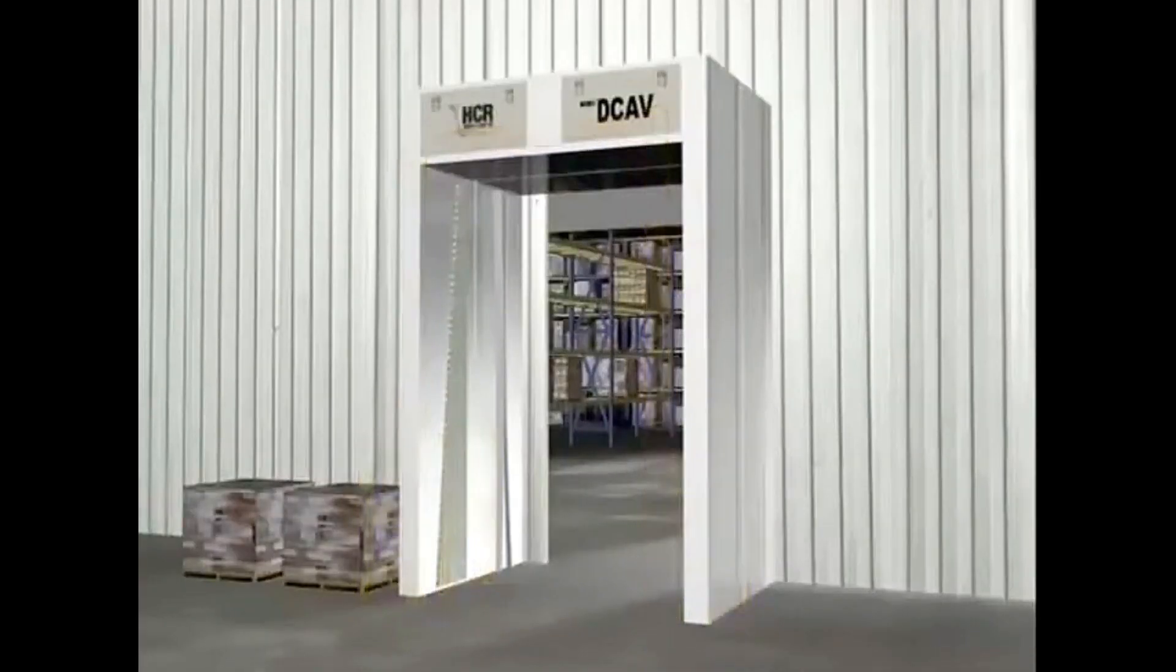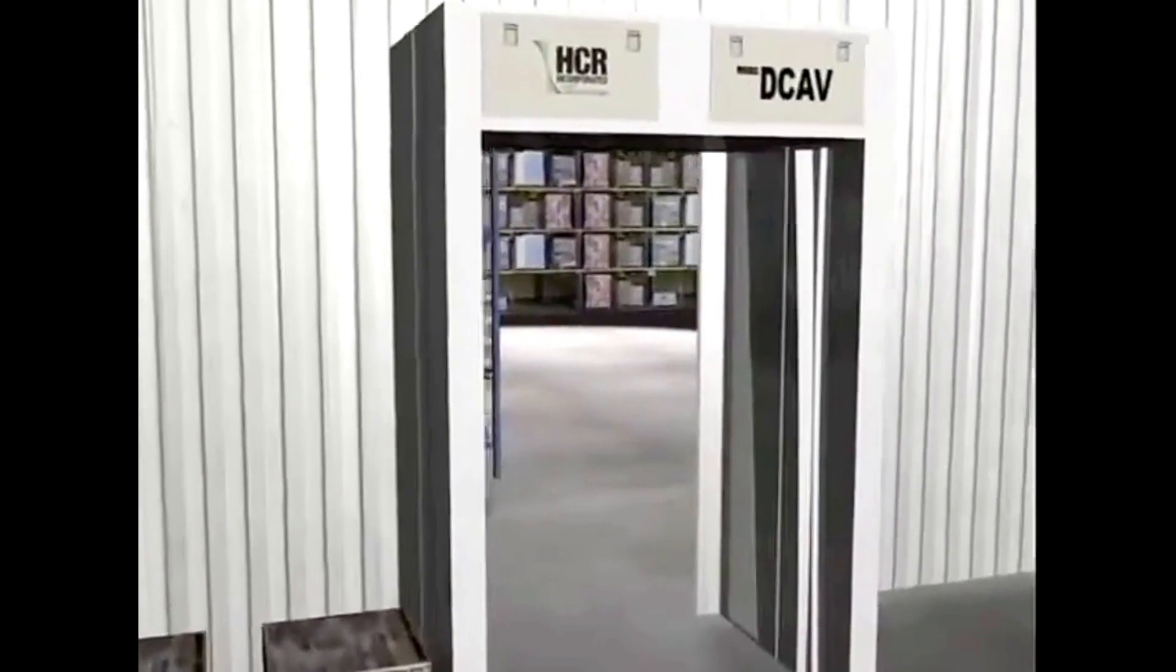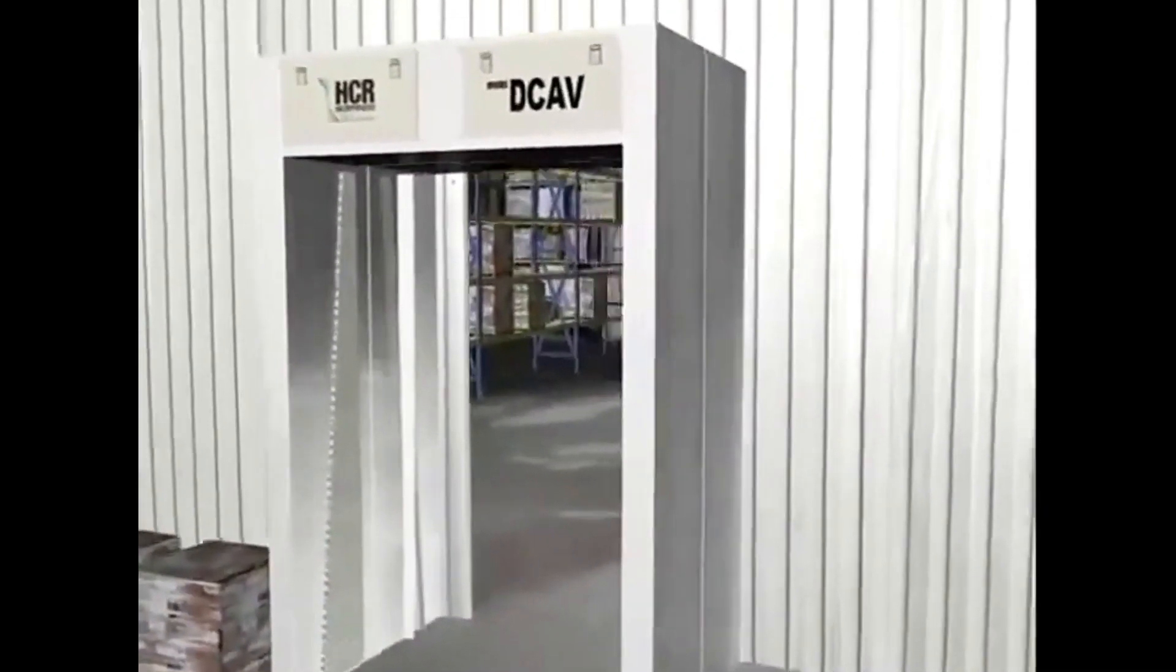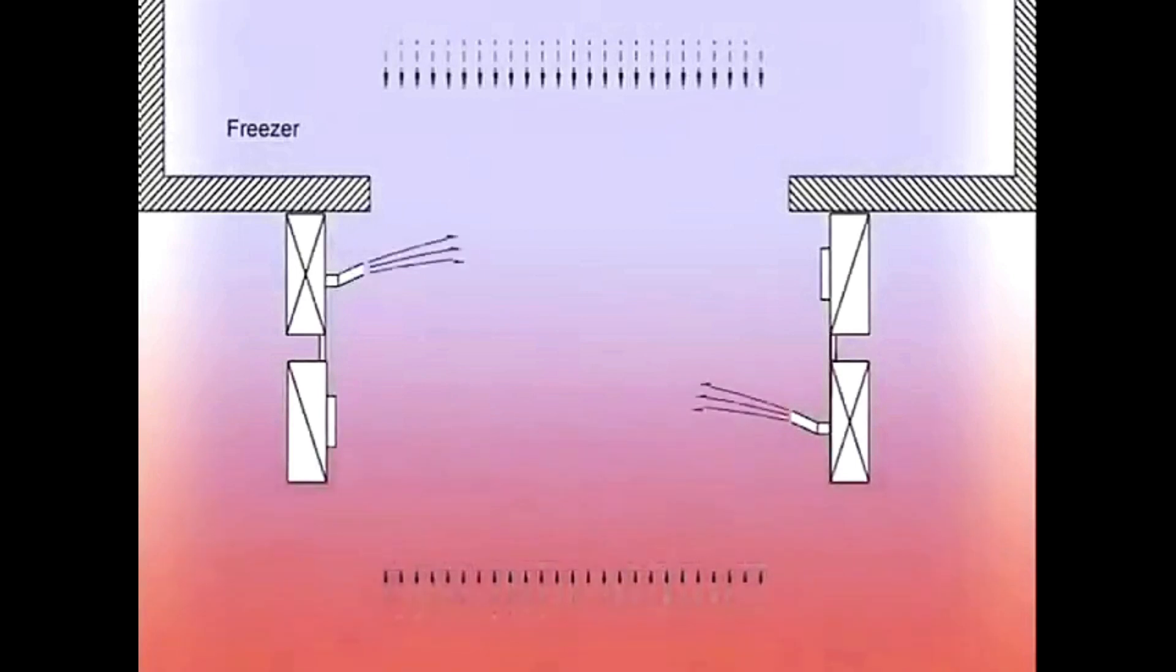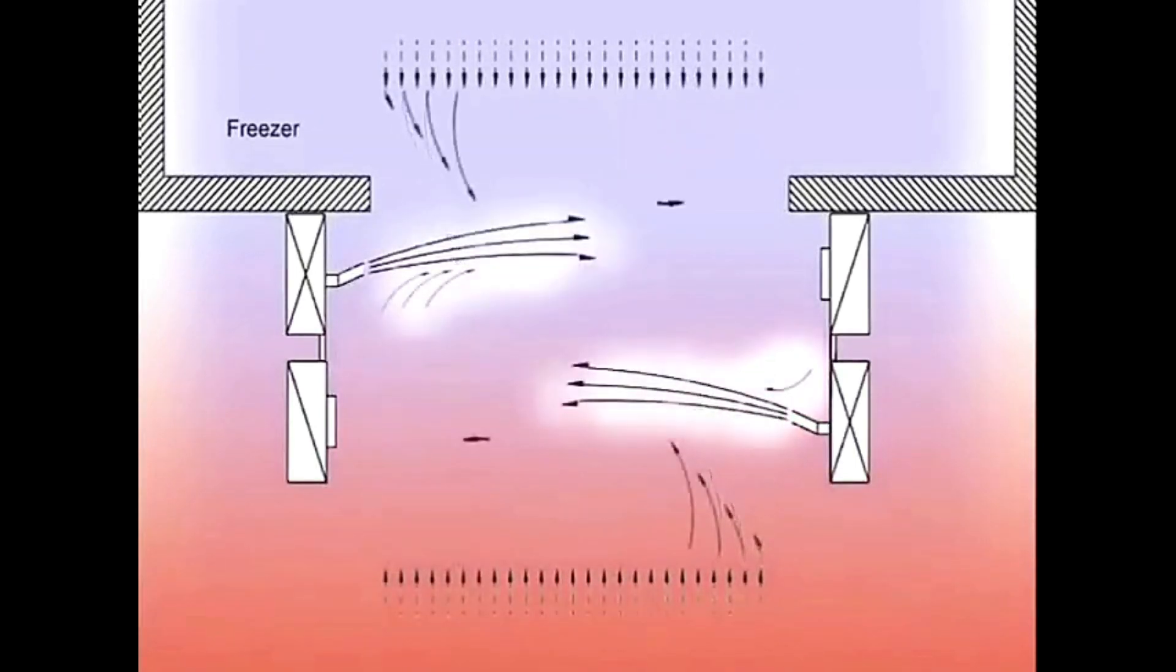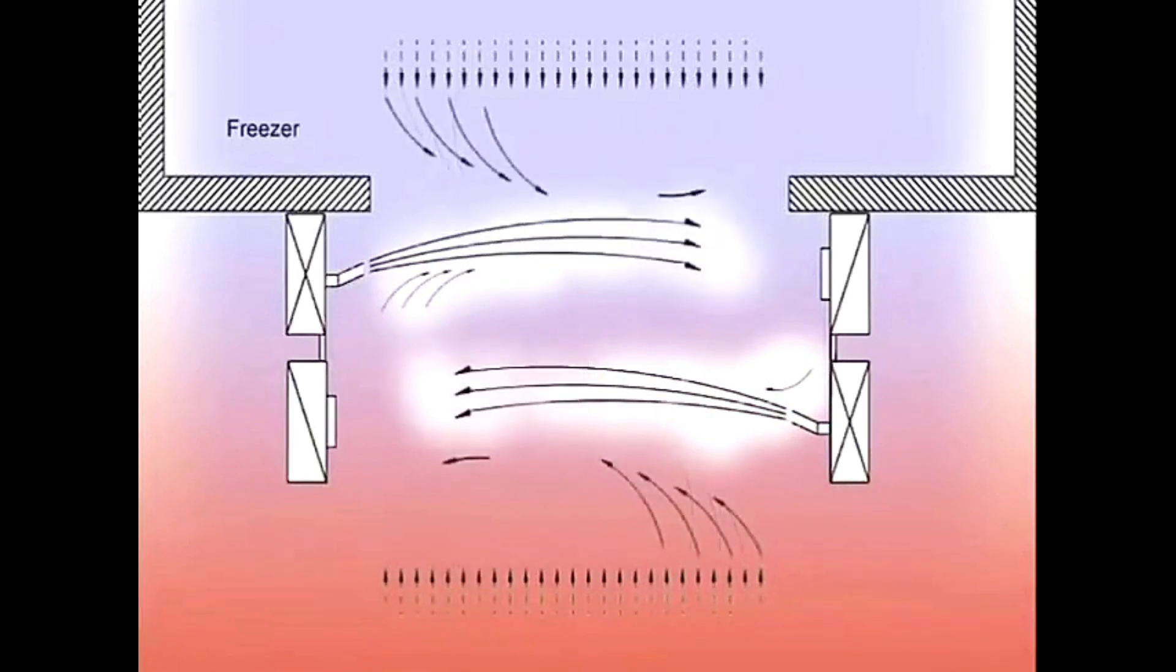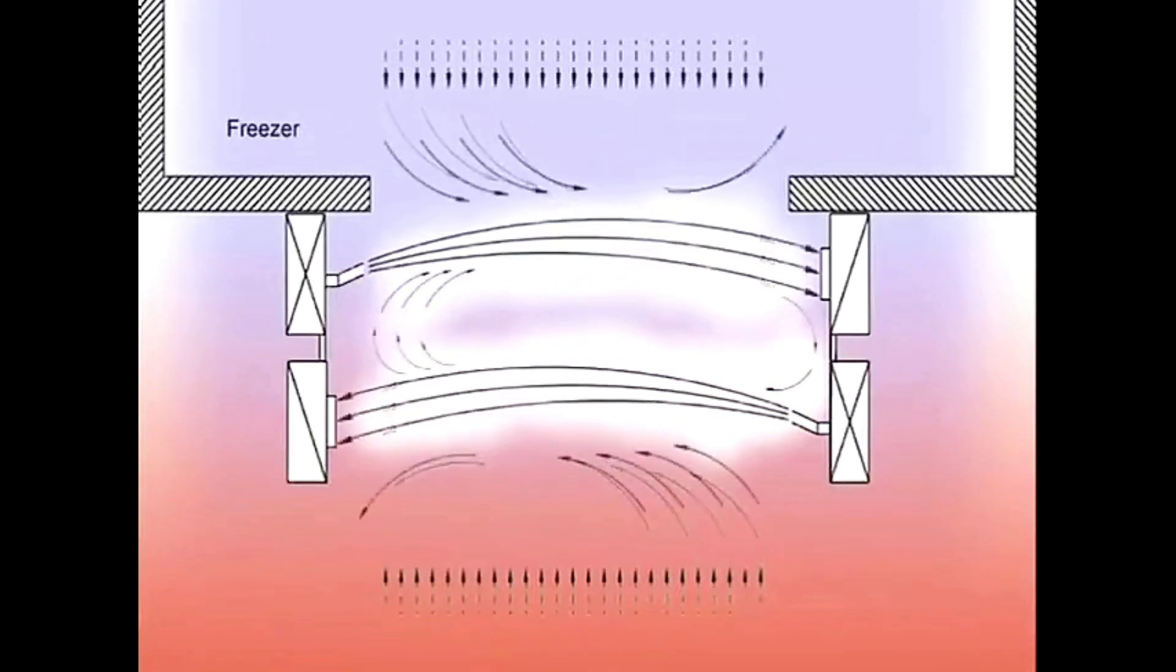With model DCAV, or double-conditioned air vestibule, the door induces airflow patterns like the single air curtain. When two are placed together and designed to work in harmony, it creates an air vestibule between the two airstreams, where the air is captured and treated to a non-frost, non-fog state. This model creates a vestibule with no visible doors.